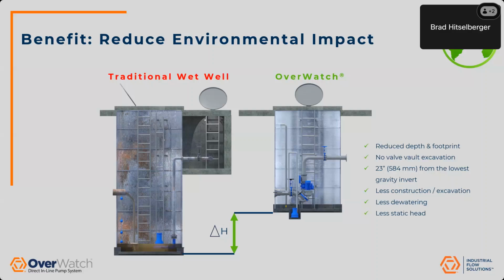Where this really, really does well is certain terrains where there's bedrock that is very hard to dig down deep into, and it's very costly to dig down deep as well. And then if you think of any places maybe out by the coast that have like a high water table issue, that is very, very costly to dig down deep with a lot of the construction that it takes and the time that it takes. There's less static head with this, less construction and excavation. What we really need is only anywhere from about 20 to 24 inches from the center line of the lowest point of gravity invert to the bottom of it. And in this picture too, you can see highlighted is that sump pump that's tied back into that low pressure side too. So this is a good depiction of what you would see with an OverWatch, a nice clean dry environment versus a traditional wet well, and the cost savings and the environmental impact with it.